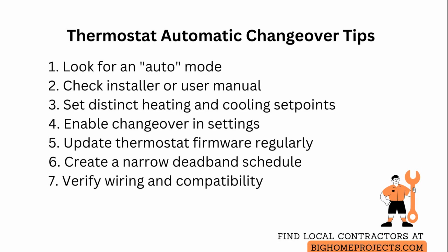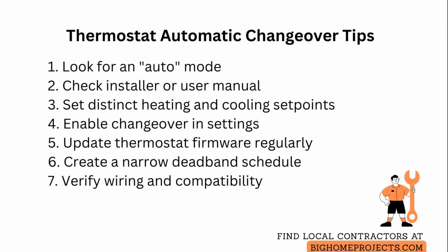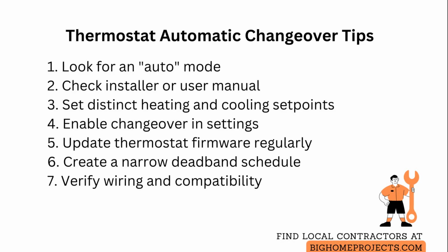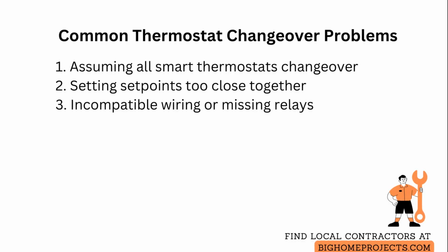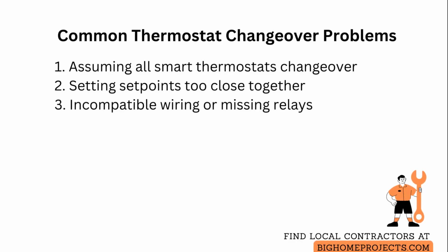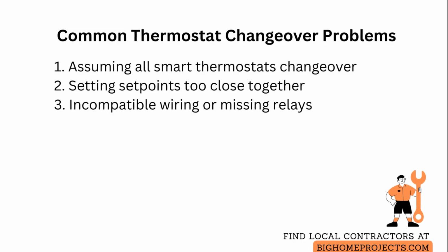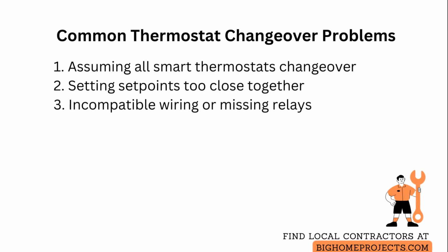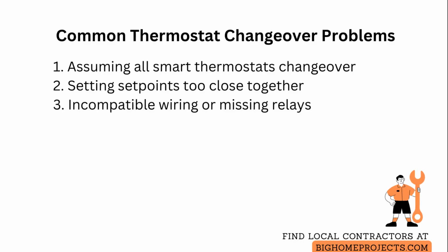Always verify the wiring and system compatibility first, because some heat pump systems require specific control logic or a dedicated changeover relay to prevent short cycling or system conflict. Common mistakes include assuming every thermostat with smart labeling has automatic changeover, which leads to unexpected system cycling. Check the exact feature list and test it on a mild day to confirm behavior.